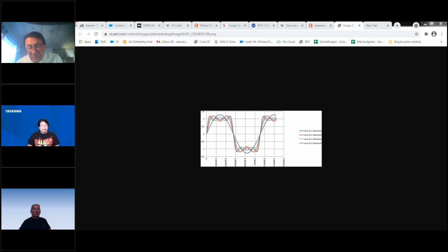And the second issue is that because of moving away from bronze impellers and to lower inertia impellers, we've now further reduced the inertia of this motor, so it's even more susceptible to the aberrations that are associated with the harmonics from the VFD waveform. And then lastly, the mandating of low VOC insulation, which means that the insulation cannot be exposed directly to water, has to be epoxy encapsulated. So now you have more thermal losses in this low inertia motor because of the VFD waveform. And now you're trapping those additional thermal losses onto the winding with the epoxy encapsulation. A concert of left turns that has resulted in significant problems in the submersible motor application.